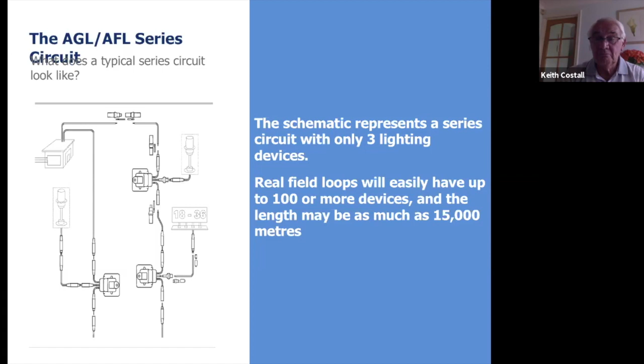Now these connectors, they have to be watertight because this equipment, both the cable, the connectors and the transformers, live under the ground in transformer pits, joined together by directly buried cable or through cable ducts. Cable ducts are part of the drainage system of the airfield. So they're all underwater, and I principally say, all waiting to fail. Because that's what happens. Over time, the equipment deteriorates in those conditions and it fails.